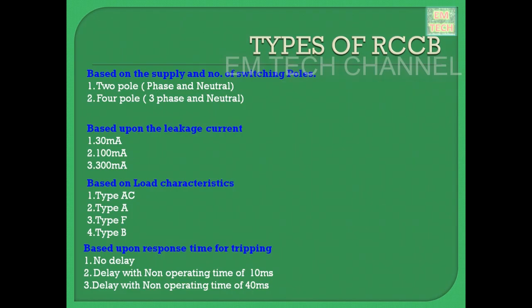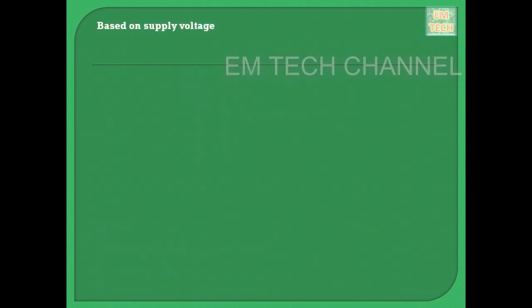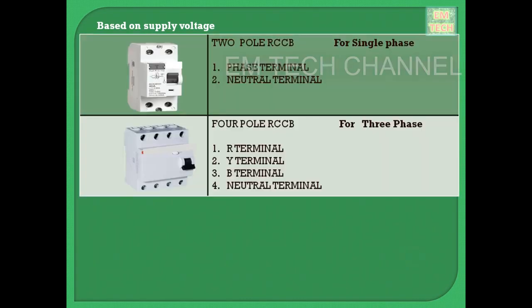Next, let us see each of the factors and its variants in detail, based on the supply voltage. First, the 2-pole RCCB. It has 2 input terminals and 2 output terminals. It consists of 1 phase terminal and 1 neutral terminal and is used in a single phase supply. And next is the 4-pole RCCB. It consists of 4 input terminals and 4 output terminals. It consists of 3 phase terminals and 1 neutral terminal and is used for a 3 phase supply.